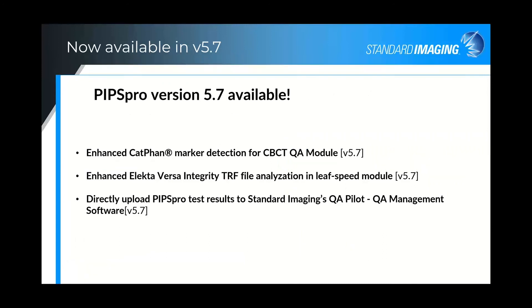We recently released version 5.7 with several enhancements: improved marker detection in the cone beam CT module for more accurate and easier key slice localization, enhanced Elekta Versa Integrity TRF file analysis for the leaf speed module, and direct upload from PIPSpro into QA Pilot, giving you a full package covering all TG142 tests.